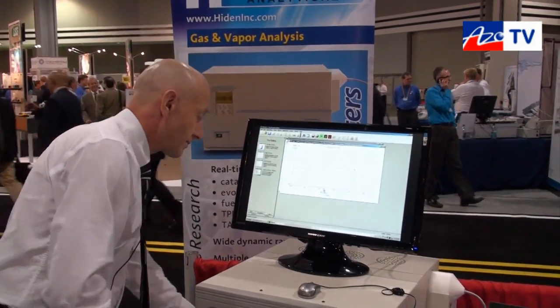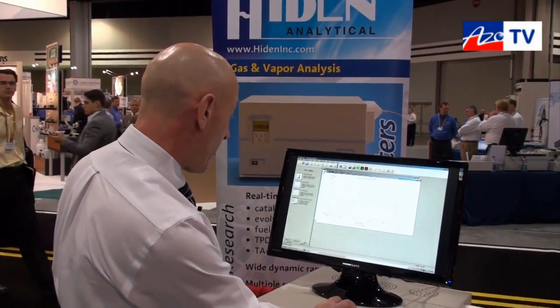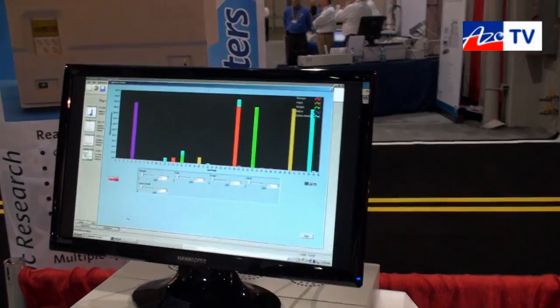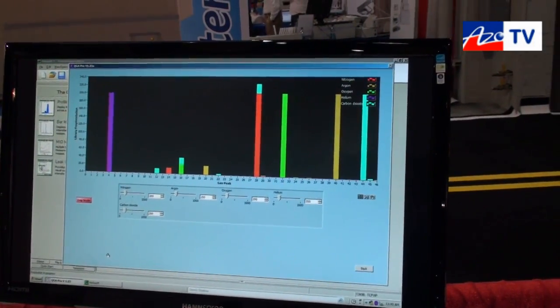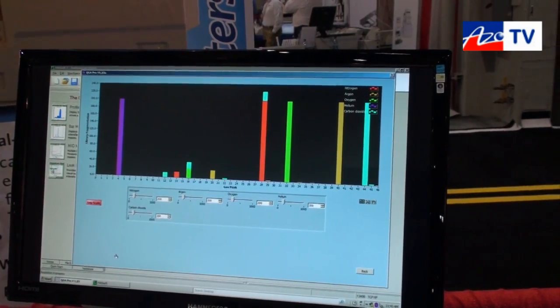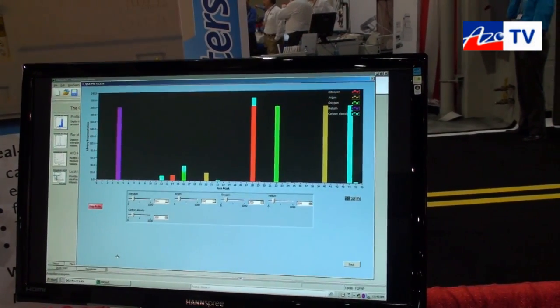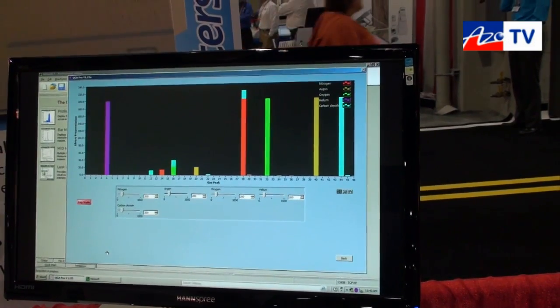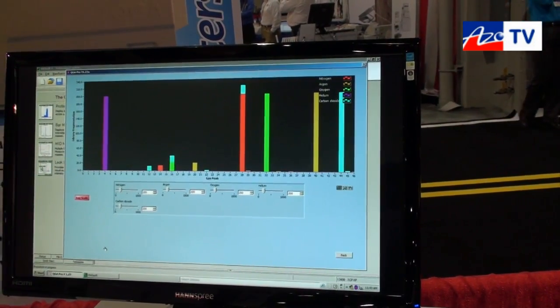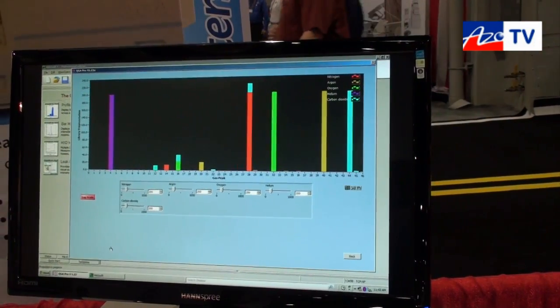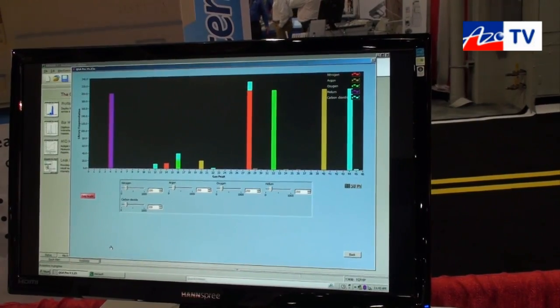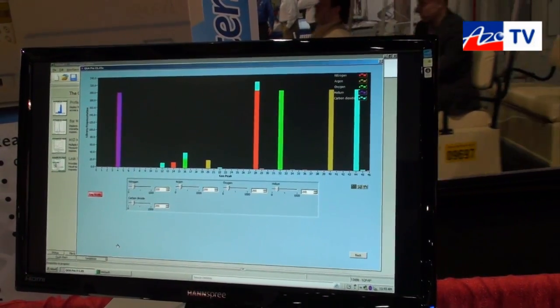We have information on that at HidenAnalytical.com. For folks looking to do truly quantitative gas analysis, along with the MassSoft 7 Professional instrument control software, we also include our QGA quantitative gas analysis software. This features a 16-peak capability — it can look at 16 discrete gases, each with up to 10 individual fragmentation peaks. The instrument deconvolutes the spectrum and indicates the absolute amount of each gas in your gas stream. We can do that for single or multiple gases, remove the background, and calibrate against a known gas mixture.